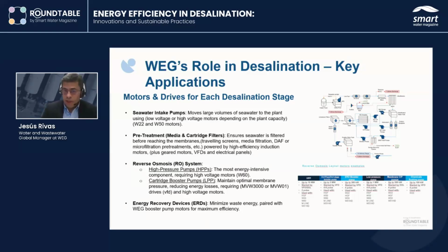Pretreatment is key for the quality of the process, with media filtration, cartridge filtration, DAF, or microfiltration, whatever the process, these are also furnished with motors and drives. Most important, the water treatment process is based on the RO process, the membrane. So the high pressure pump, the low pressure pump, the booster pump, all these main line components, including the ERDs, are responsible for the main part of the energy consumed by the desalination process.